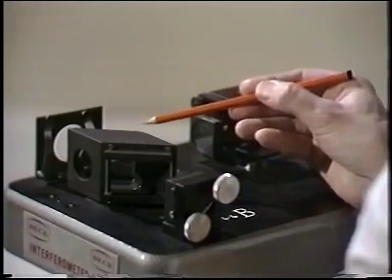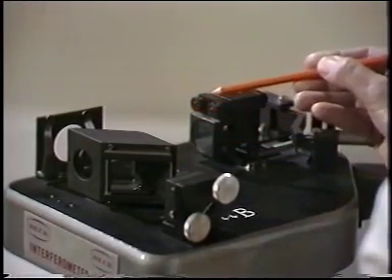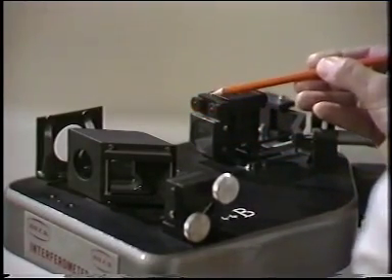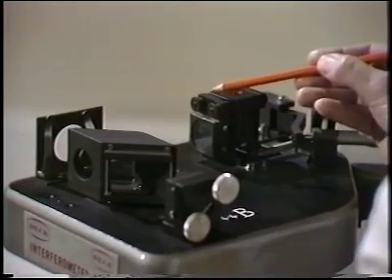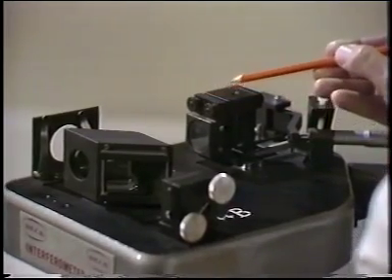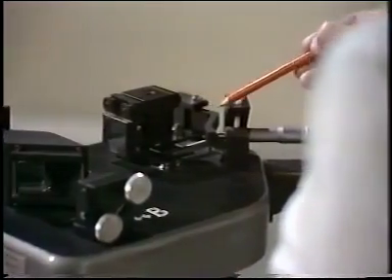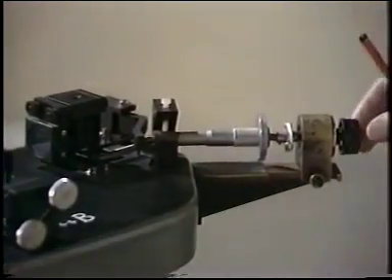In constructing a Michelson, an awful lot of thought must go into the moving mirror. It must move nice and smoothly. It must move smoothly over distances of the order of a wavelength of light. It would never do for it to jerk and jitter all over the place. In our equipment, it's this beam which impinges on the movable mirror, which can be adjusted back and forth. And this is done by means of a system of levers coupled to a micrometer screw.